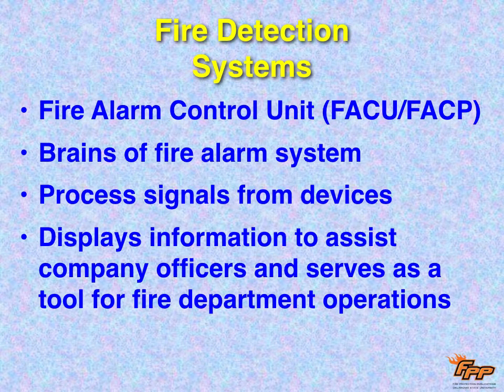So the fire alarm control unit, as I said, is like the brains. It processes all the signals that come from the devices, both those that are input, and then it sends out messages to those that are output. So the detection device sends a message to the brains, and then the brain sends a message to the notification devices, and sets off alarms, bells, strobes, whatever.